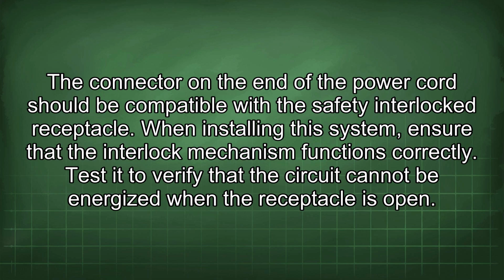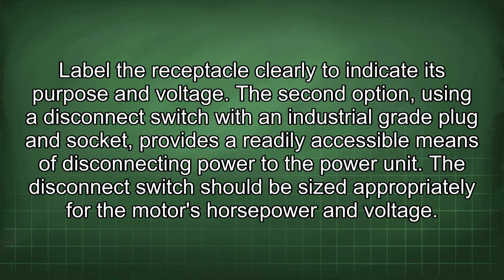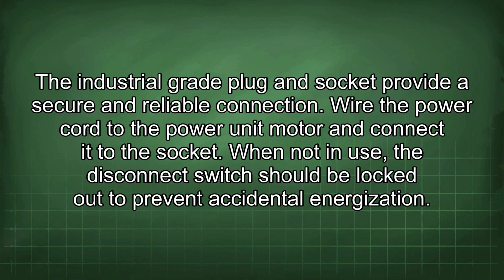When installing this system, ensure that the interlock mechanism functions correctly. Test it to verify that the circuit cannot be energized when the receptacle is open. Label the receptacle clearly to indicate its purpose and voltage. The second option, using a disconnect switch with an industrial-grade plug and socket, provides a readily accessible means of disconnecting power to the power unit. The disconnect switch should be sized appropriately for the motor's horsepower and voltage. The industrial-grade plug and socket provide a secure and reliable connection. Wire the power cord to the power unit motor and connect it to the socket. When not in use, the disconnect switch should be locked out to prevent accidental energization.